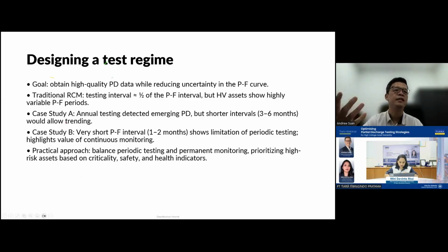Then you ask yourself, what is a case study? Do I have a similar case study for my switchgear? Annual testing detects PD, but a shorter interval allows trending. If I go back every 3 months, I can see the PD - I know if the signal will increase or maintain. Maintain maybe means it's not so bad, it's within control, I can wait a while. But if I go back every 3 months and the signal is increasing, that's a sign I need to take action ASAP.